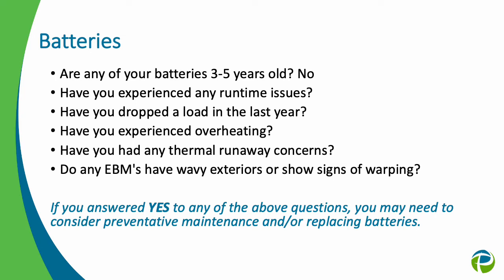Are your batteries 3 to 5 years old? Have you experienced any runtime issues? Have you dropped a load? Have you experienced overheating? Do you have any thermal runaway concerns? When we're talking about a bigger battery cabinet, thermal runaway is where one battery will overheat, and because all of these batteries are daisy chained or connected together, if that one battery overheats, it's like a fire. It just spreads through the other batteries. So one overheating battery can cause all the batteries to overheat.